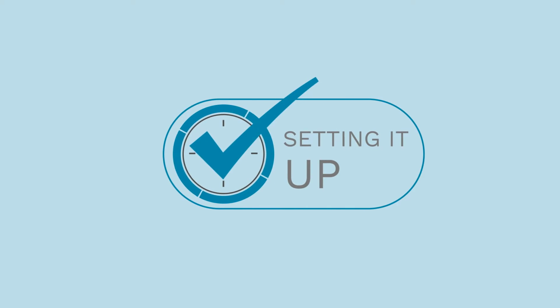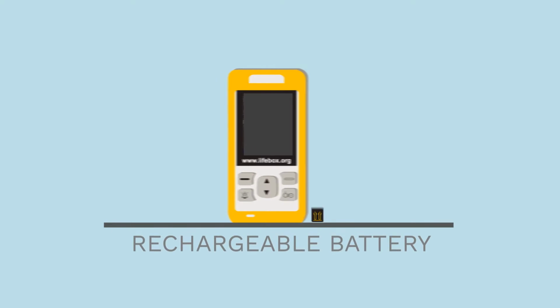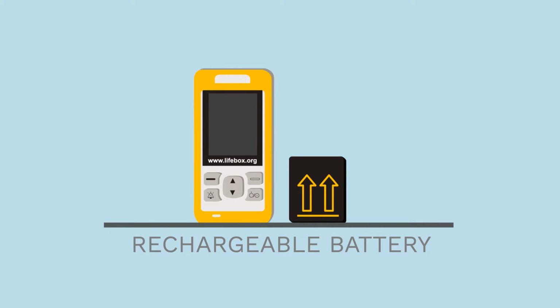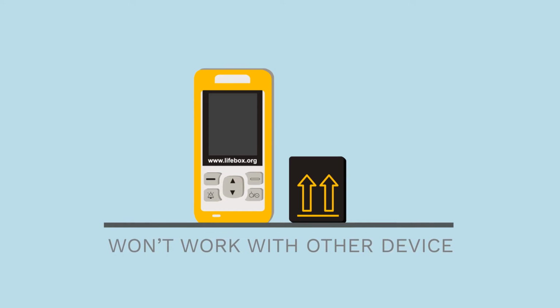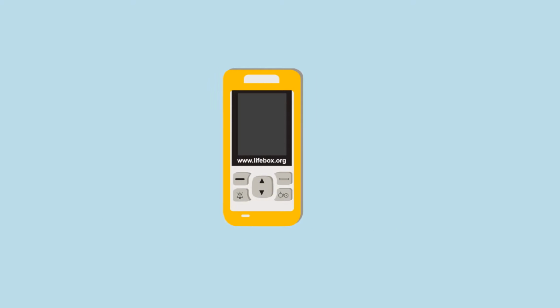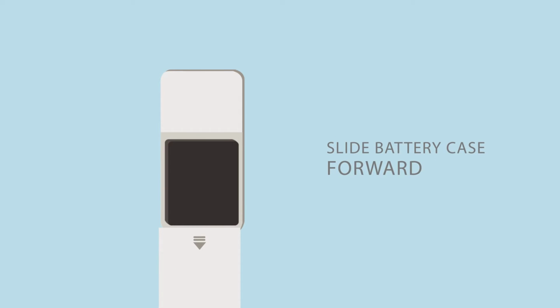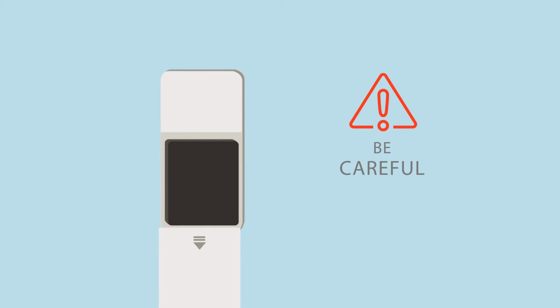Now that we know what's included in a Lifebox, let's take a look at the steps involved in setting it up. Now, the first thing you might recall is that the Lifebox oximeter is run off a rechargeable battery. It's specially designed to fit the Lifebox oximeter, so it won't work with any other device. To install the battery, first you need to open the battery case. Turn the oximeter so that the screen is facing downwards and peel back the yellow cover until you can see the raised arrow. Rest the oximeter screen side down on a flat surface. Place your thumbs on the raised arrow, press down firmly and slide the battery case forward. Be careful not to press your fingers on the screen when you do this. Too much pressure and the screen might crack.